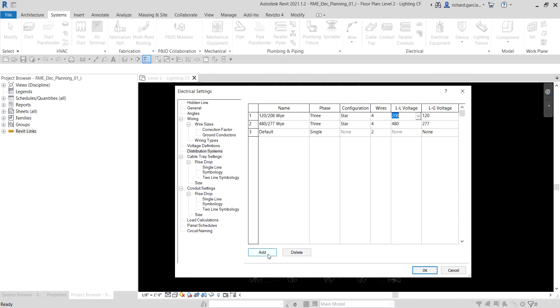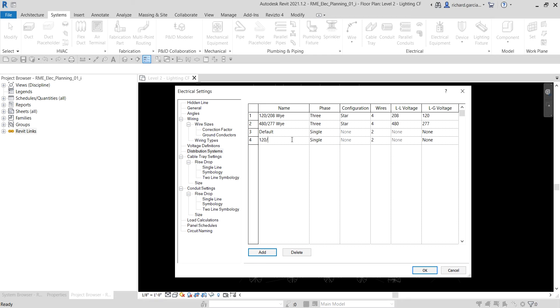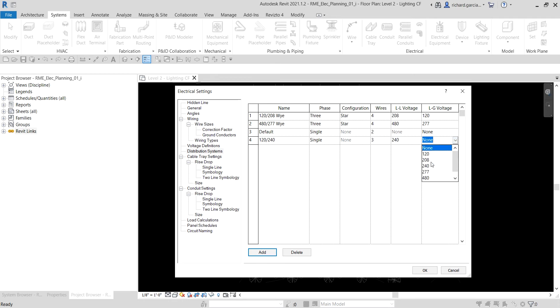Let's add a distribution system. I'll click Add and name it 120/240. I'll set the phase to Single, the number of wires to 3, the LL voltage to 240, and the LG voltage to 120 — that's why the name is 120 over 240. That's our new distribution system.